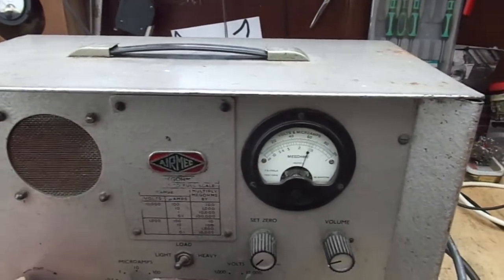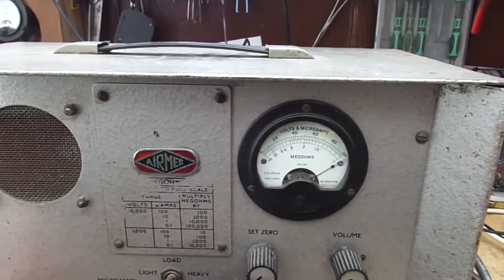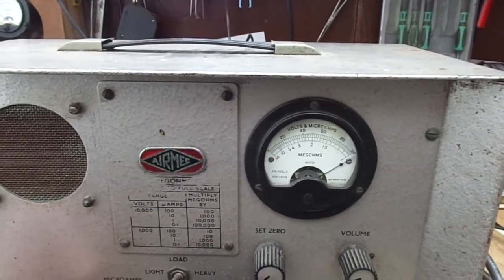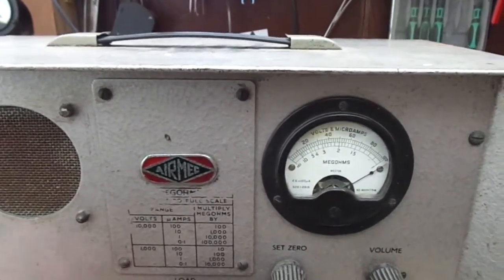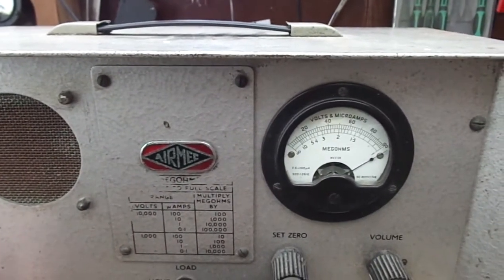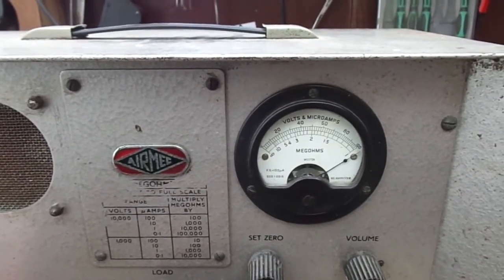Let's cut it short and go. Alright, but you see there on that lower range, not so good. We're on one microamp now. Let's see, it's just bottoming out. If that needle jumps, the insulation is breaking down.